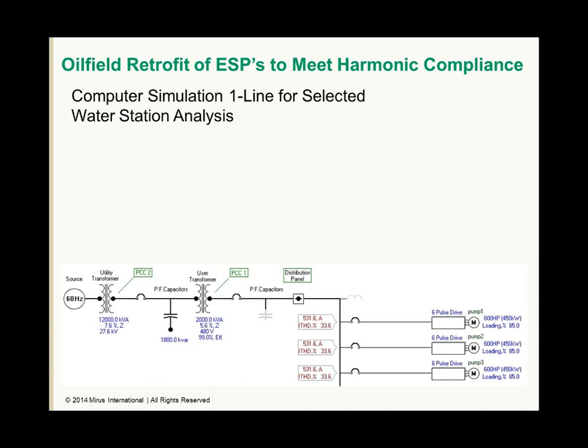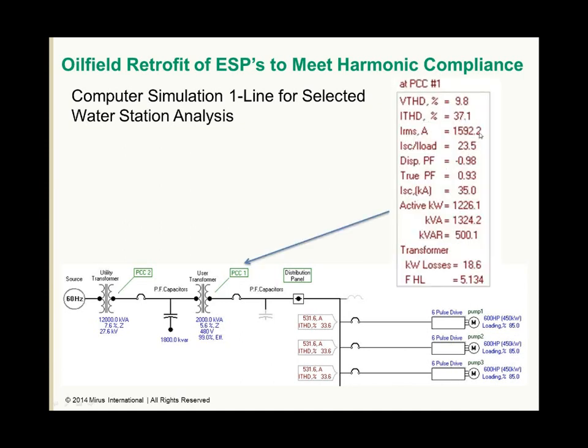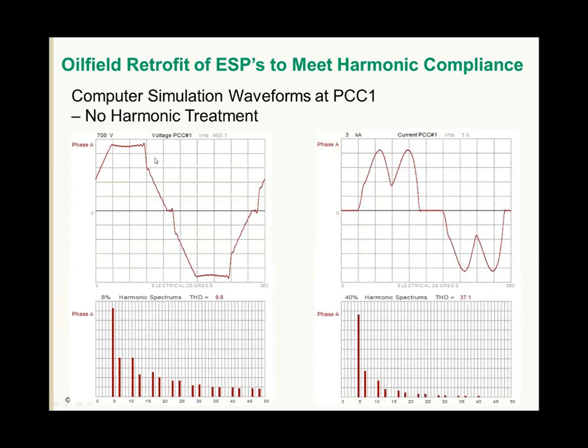Computer simulations were done to show how the existing 6-pulse drives were the cause of the high current and voltage distortion. So we show a couple of 6-pulse drives here running at 85% load. The current distortion is 37%, voltage distortion at 9.8%. Here we can see the simulation's voltage waveform and the spectrum of the harmonics of the voltage with 9.8% voltage distortion, so this is still even less than the actual voltage distortion at the site.